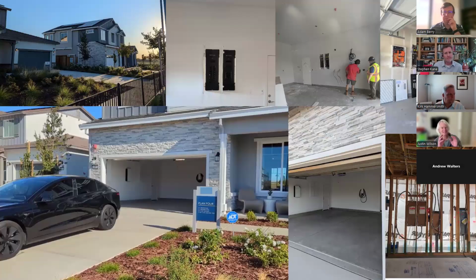The other thing I see is there are smaller panels if we focus not just on 200 amps. Maybe a house has a 100 amp panel. Does SPAN have a 100 amp panel, or is there one on the way? You can downsize any of our panels to the breaker size, classic trade sizes on the main: 200, 175, 150, 125, 100. So the same form factor with the large bus rating can apply to any service size with a main breaker swap in the field.